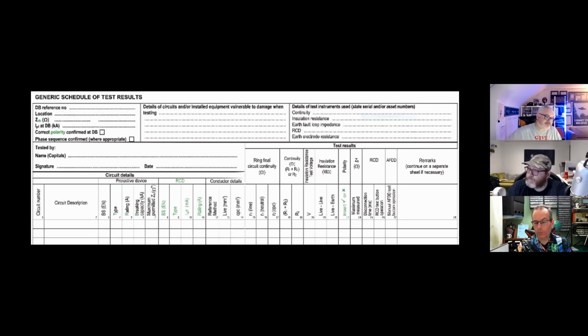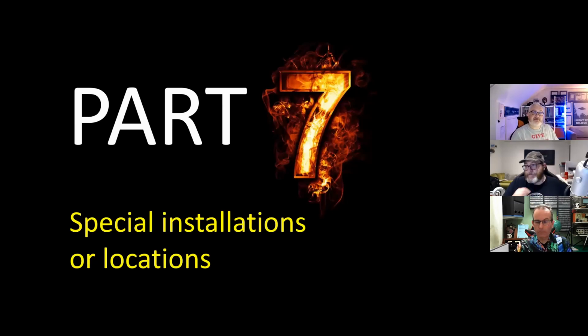Wow. Interesting - so there's ZS, polarity, RCD, AFDD, remarks, but there is nowhere to record any fault current other than at the DB. So you still cannot record the end of the final circuit short circuit current. Yet the wording of that regulation we just went to infers that you have to record it, because that's an addition to that title. But yeah, okay, that's enough of me.